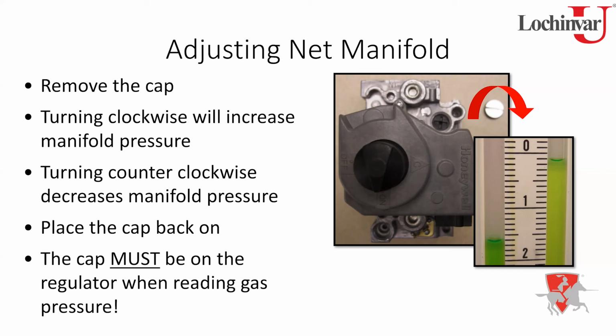Now, if you're fast, you can do that. If you're like me, when I pull that cap off, it's typically going to fall down somewhere in the cabinet, roll across the floor, and I can't find it. And it's going to lock out before I can get that cap on there. So just have some patience with it when you do that. Also, if there's a drain anywhere near the heater and that cap hits the floor, it's probably going to go down the drain. So just be aware of that.